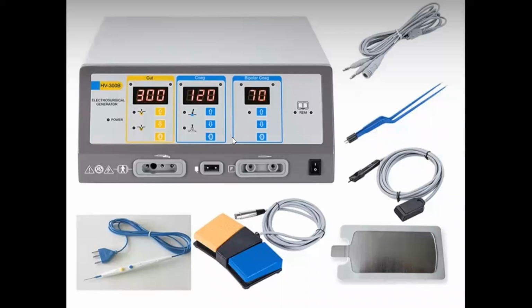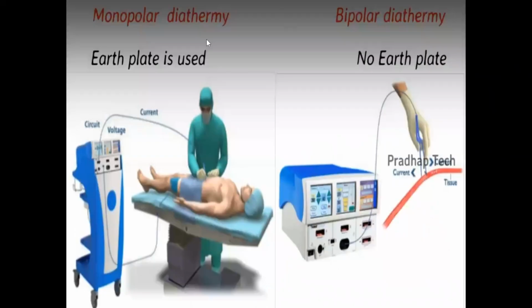Let's say you're using bipolar. Bipolar only coagulates. So bipolar, you see these two things, these two sockets will go here, one for each pole, and this end will be connected here. Go to the OT tomorrow, please have a look at it. Okay, this is one picture that explains it all. So one machine is used for both monopolar and bipolar, depending on where you connect it. Next. Monopolar diathermy, bipolar diathermy.